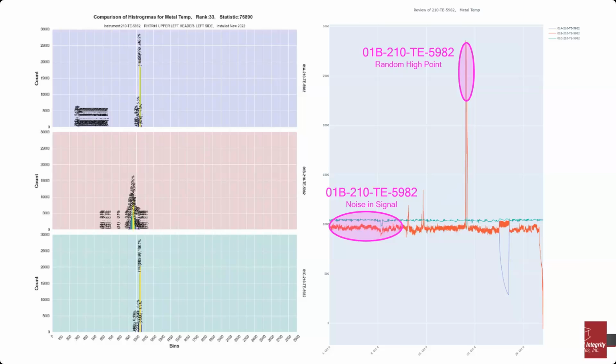When we installed our instruments, we reached out to both SI and also EPRI to get a recommendation for which components to monitor, because you can't monitor everything, obviously. You have to prioritize and pick the highest risk components. That could very well depend on your design of your unit and your operational profile. So you can certainly tailor that to your specific unit and come up with a list that makes the most sense and prioritize the components. And that's what we did.